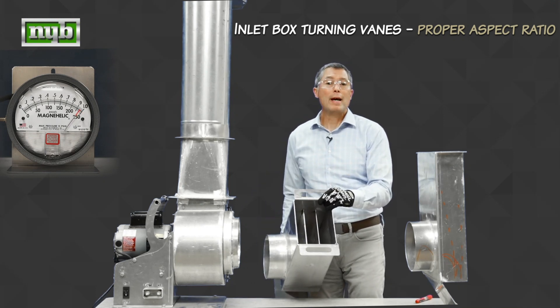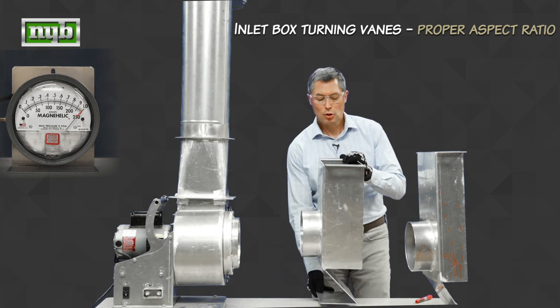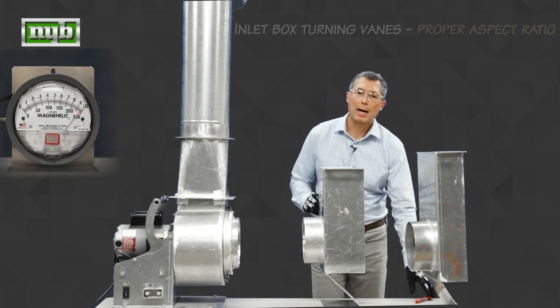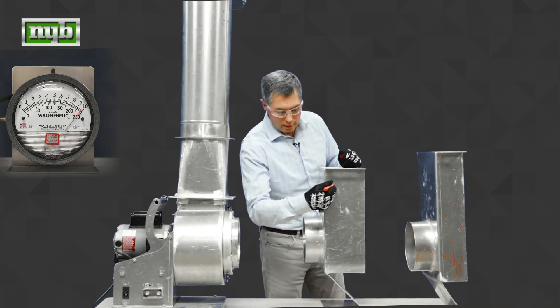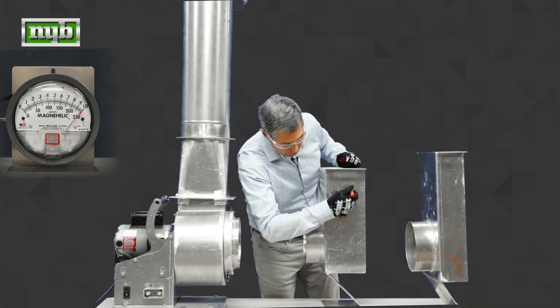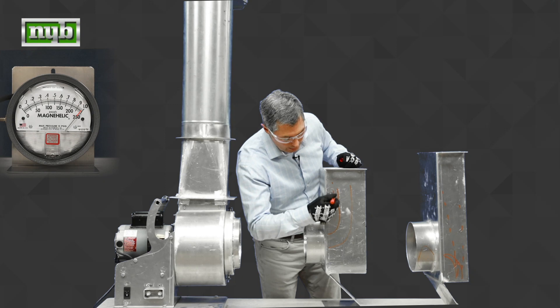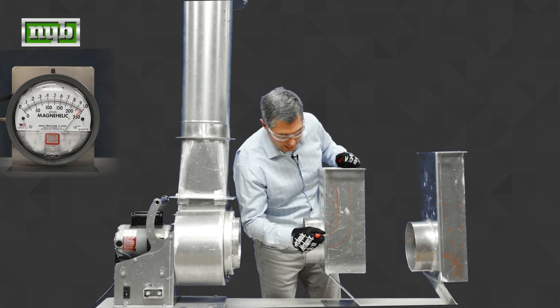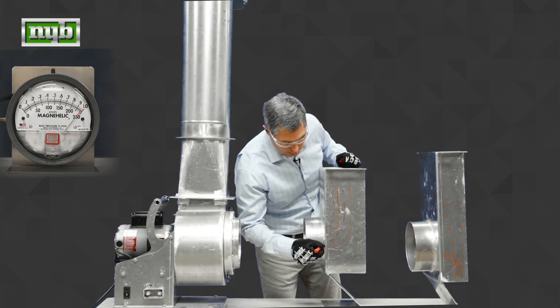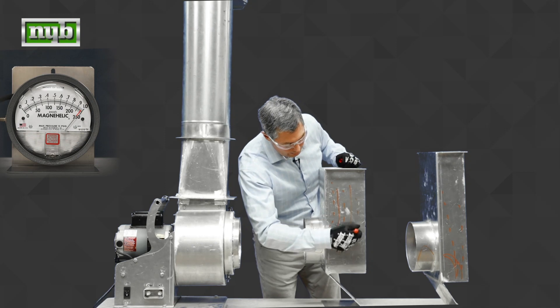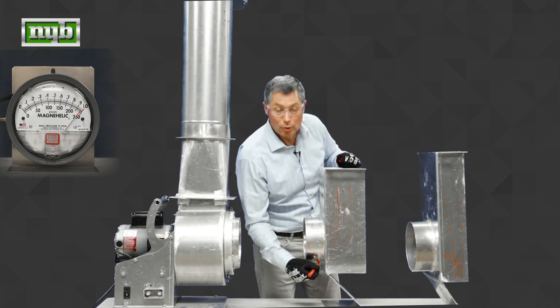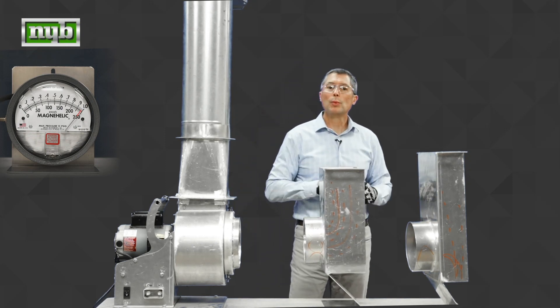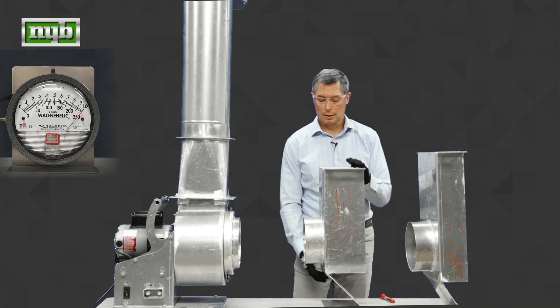Secondly, we've added turning vanes to this inlet box. And those turning vanes actually break the box into three sections. That allows the air to come in, load the top, air to come into the middle, load the middle, air to come into the bottom, load the bottom section of the wheel. Let's see what happens when we use this box opposed to this box.